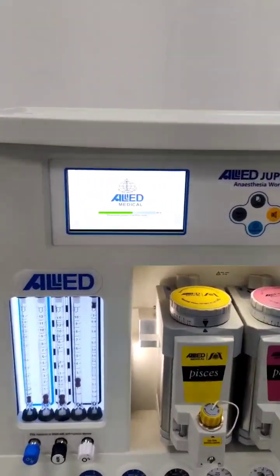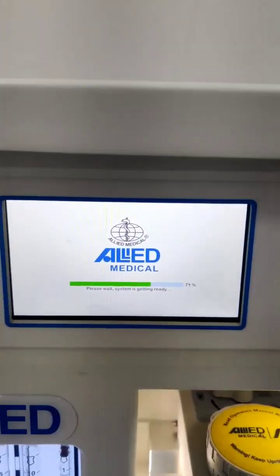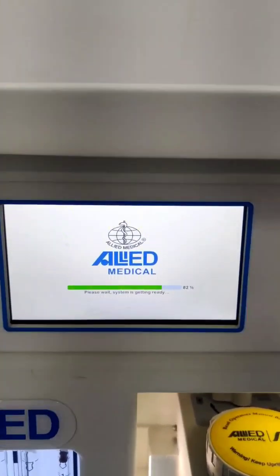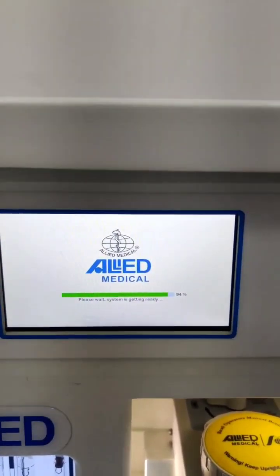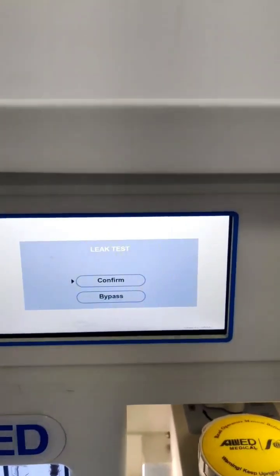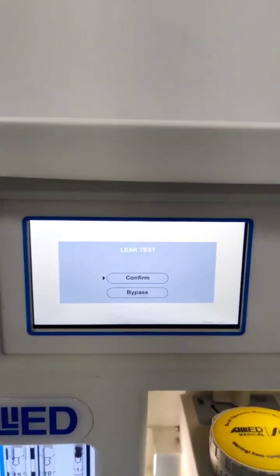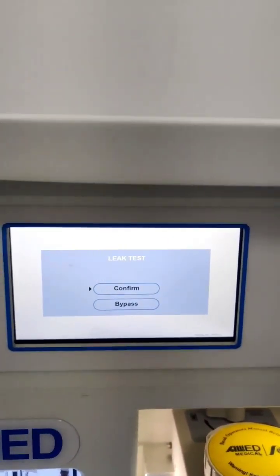So it does the self test at the start, and if there is any error, that is the self diagnosis test. If there is anything wrong with the circuitry or the pneumatic part, that error will be shown, and it will show you the leak test window. If you want to do the leak test, you can select the confirm key. Otherwise, if you don't want to do it, you can bypass it.